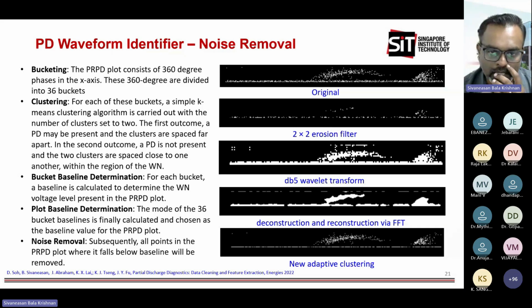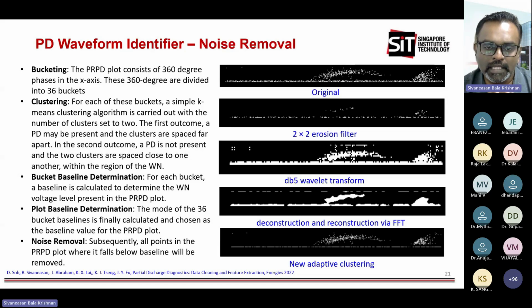This method determines the baseline where the noise occurs for every individual plot, and then we subsequently remove it. The idea is, if there's potential for a PD pattern, we do white noise removal by hovering the data points over the white noise. If you have two clusters of points, we determine the white line baseline, and anything below that we remove.